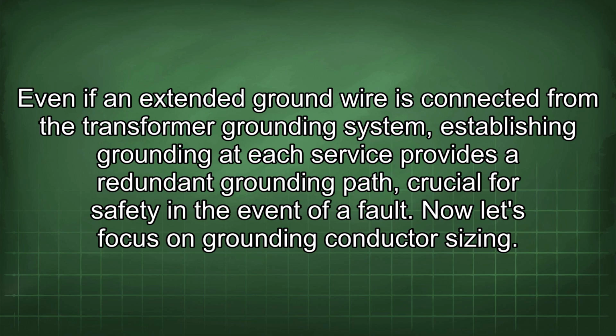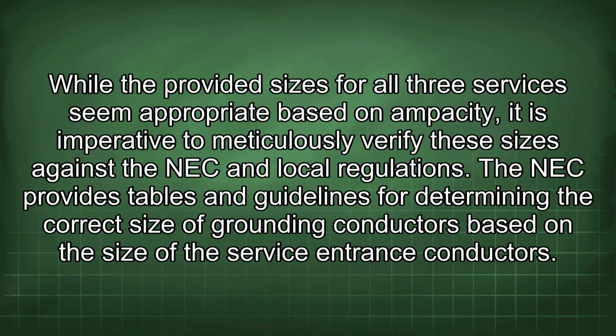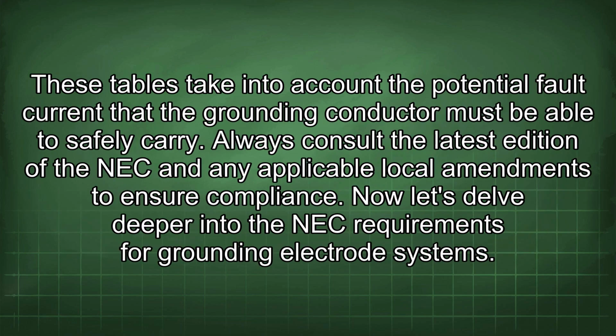Now let's focus on grounding conductor sizing. While the provided sizes for all 3 services seem appropriate based on ampacity, it is imperative to meticulously verify these sizes against the NEC and local regulations. The NEC provides tables and guidelines for determining the correct size of grounding conductors based on the size of the service entrance conductors. These tables take into account the potential fault current that the grounding conductor must be able to safely carry. Always consult the latest edition of the NEC and any applicable local amendments to ensure compliance.